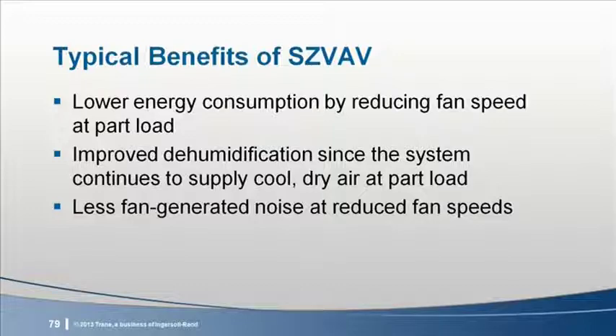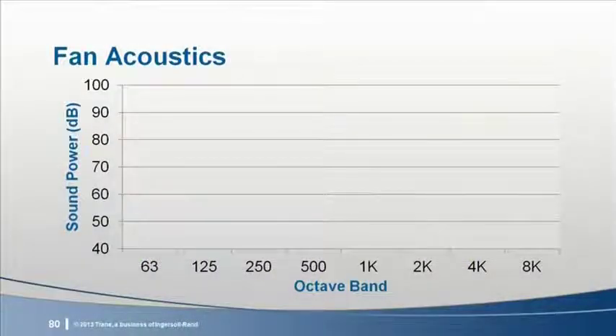In addition to energy savings and improved dehumidification, another benefit of single-zone VAV systems can be the part-load fan characteristics related to acoustics. Air distribution equipment, including fans, ductwork, and diffusers, have a significant impact on background sound within conditioned spaces. Most sound generated by a fan results from high-velocity air passing through the fan wheel and housing. As the fan motor speed decreases, the sound level will decrease as well. This analysis shows a sample airfoil fan.